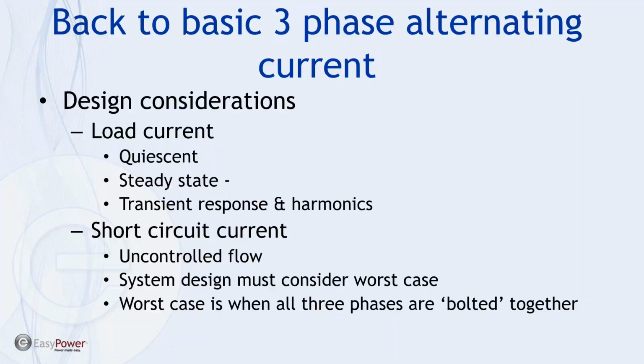The other type of consideration we look at when we do a new design is a short circuit current. And the problem there is this is uncontrolled flow, and our main focus is to make sure that the system will survive the worst case and, if at all possible, be able to protect itself. And that worst case, frankly, is when all three phases are bolted together as far as the short circuit current.